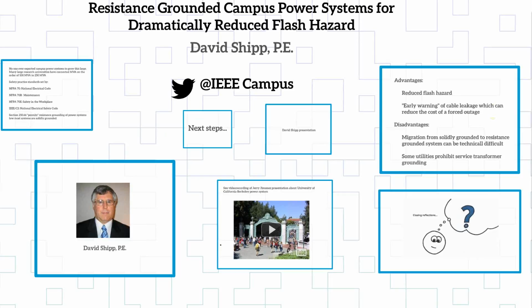So I've done this, and I've looked at it in paper mills, the steel mills, and a few places in universities and other places. And at the 15 kV level, it makes a world of difference. What we're trying to do is I'm starting to do it right now on offshore oil platforms at the same voltage level. And I keep telling people, I don't care what your industry is, the laws of electricity apply, whether I'm on the space station or an oil industry 8,000 feet down a hole, or I'm on a university campus, the same theories apply. Now, there's some variations, obviously, that you have to fit into your requirement, but it's certainly doable. And where I'm coming from, Michael, is that I came from the service part of the industry, not the new equipment design necessarily.